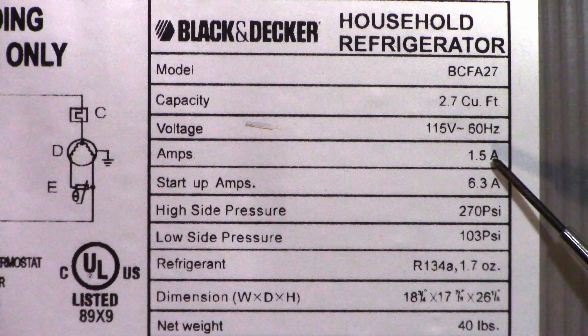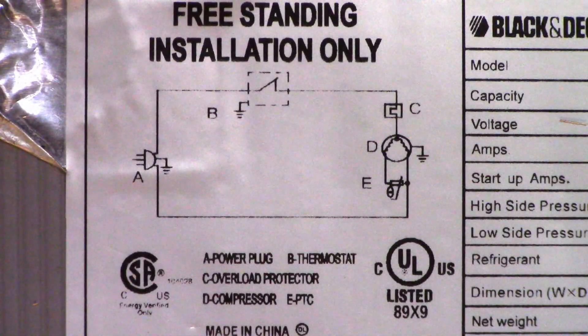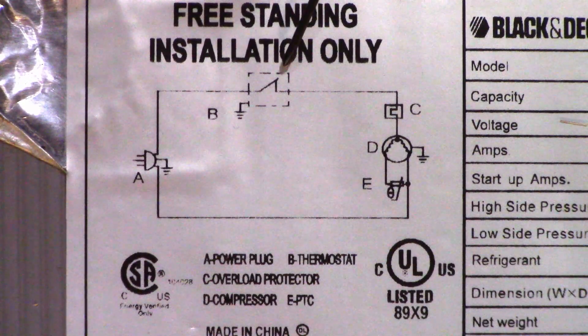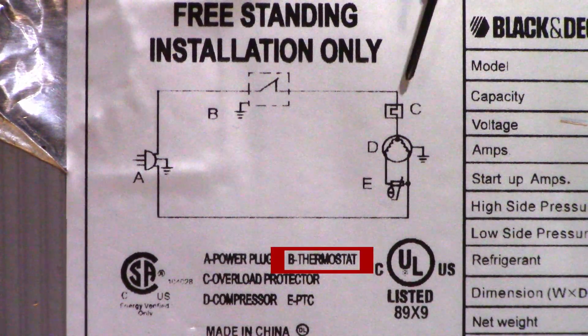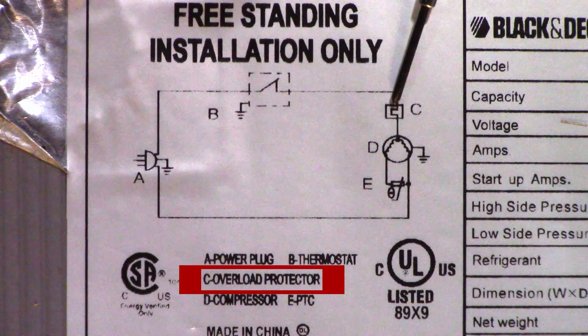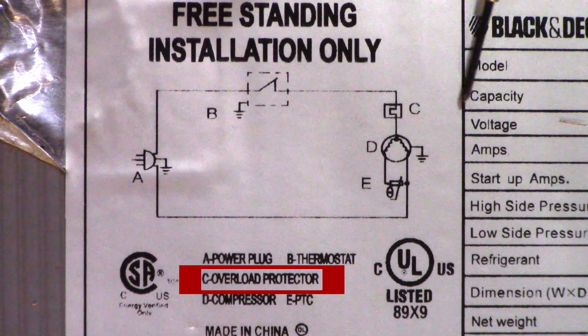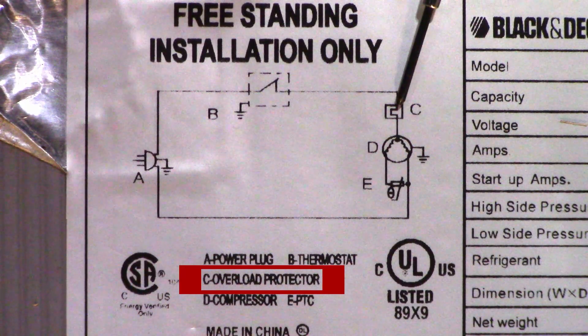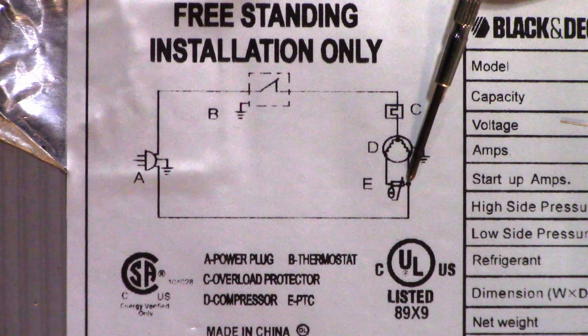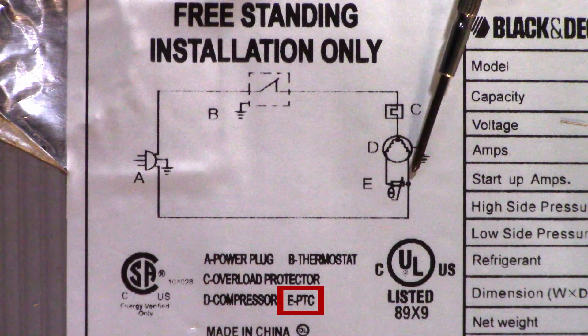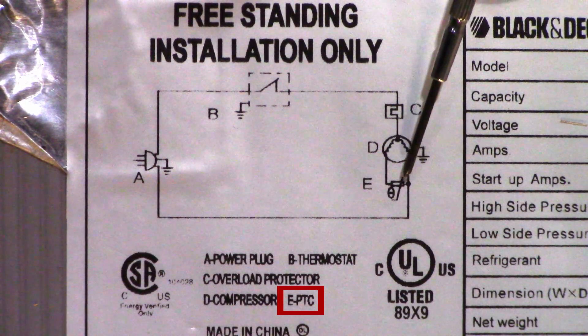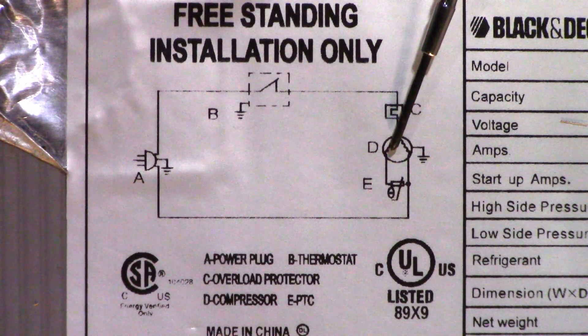Looking back at the schematic, we know the thermostat's good because the compressor is drawing power. The thermal cutout, which is meant to act on current over 1.5 amps for a long period of time, is opening. So I'm hoping we just have a bad start thermistor right here. Let's go ahead and open the little box on the side of the compressor and see what's in there.